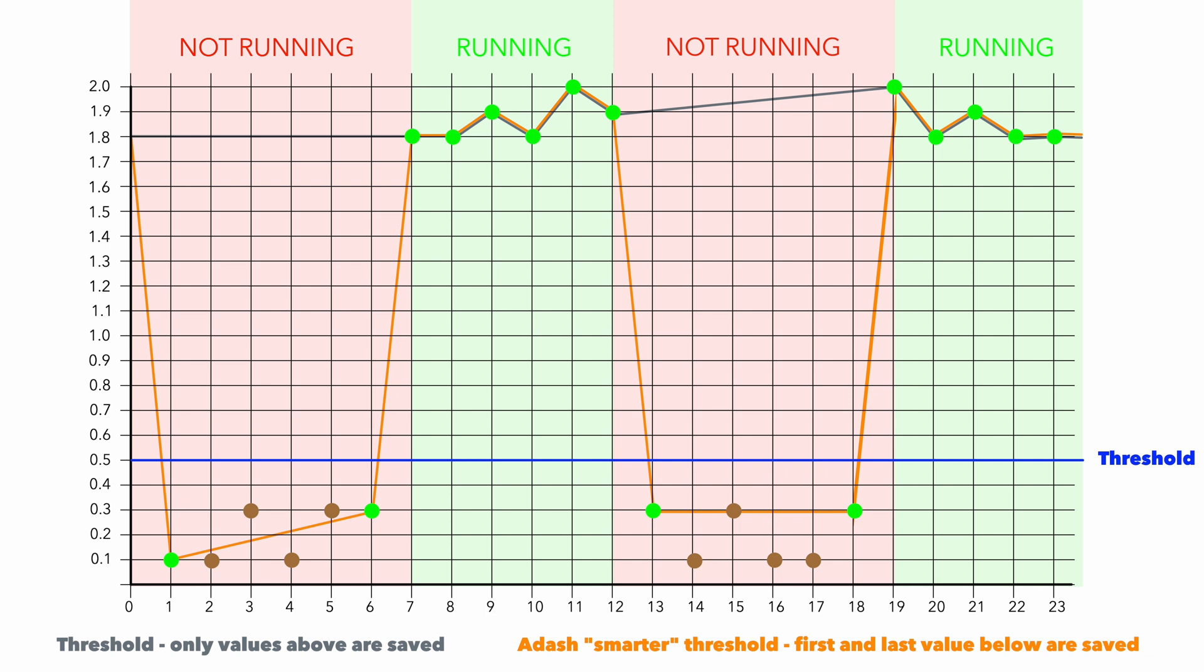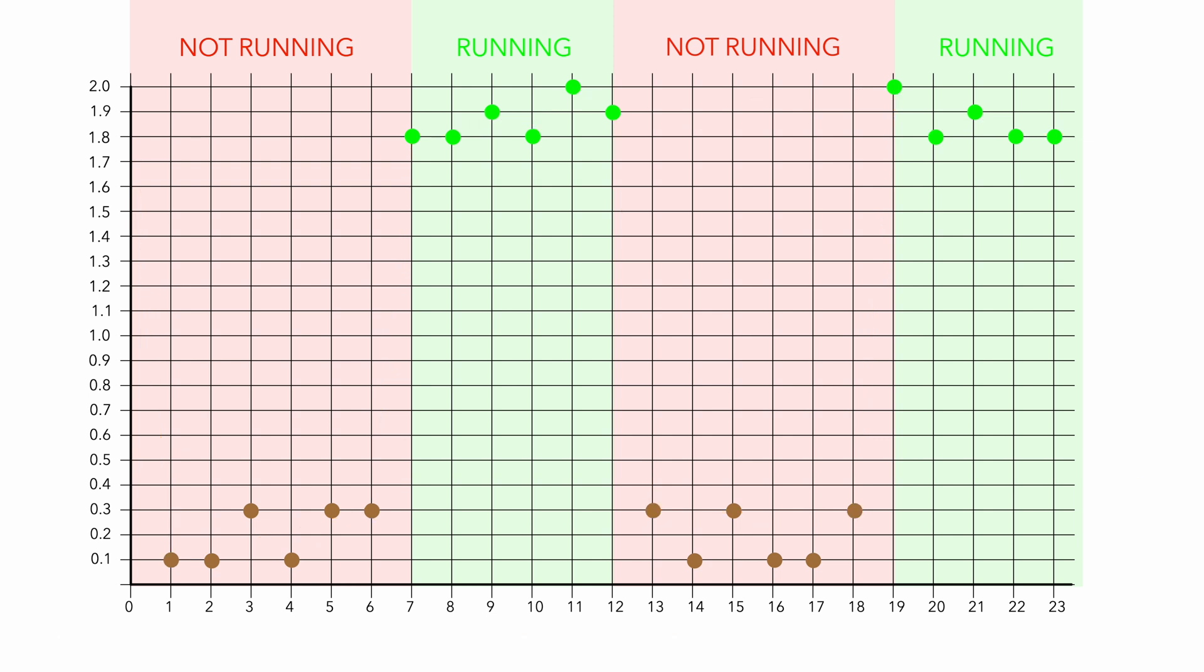If you will set it improperly, there can be a lot of values saved. You can see it in this example. If threshold value is set to value 0.2 mm per second, you can see that noise values are oscillating around this point up and down.